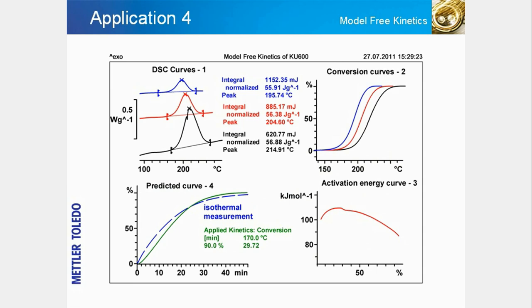Kinetic analysis is used to study the rate at which a reaction proceeds. The slide summarizes the steps involved in kinetics analysis using model-free kinetics, or MFK. The method is based on several dynamic DSC measurements. In step 1, the exothermic reaction is measured by DSC at three or more different heating rates, and the reaction enthalpies are determined by drawing suitable baselines and integrating the areas under the peaks. In step 2, the data from step 1 is used to calculate conversion curves that show the extent of reaction as a function of temperature for the three heating rates.